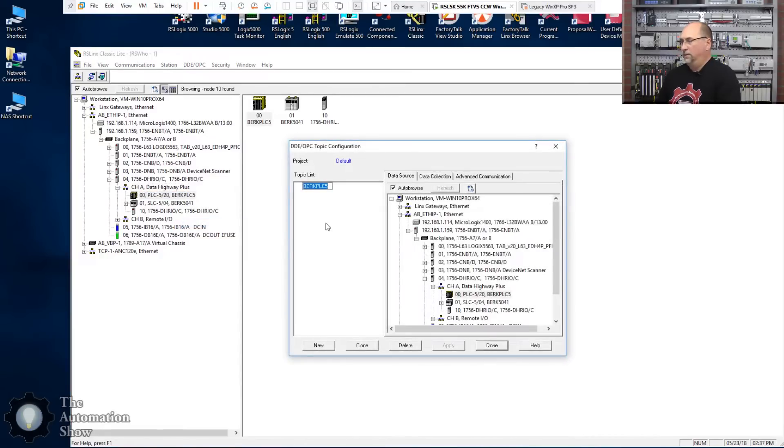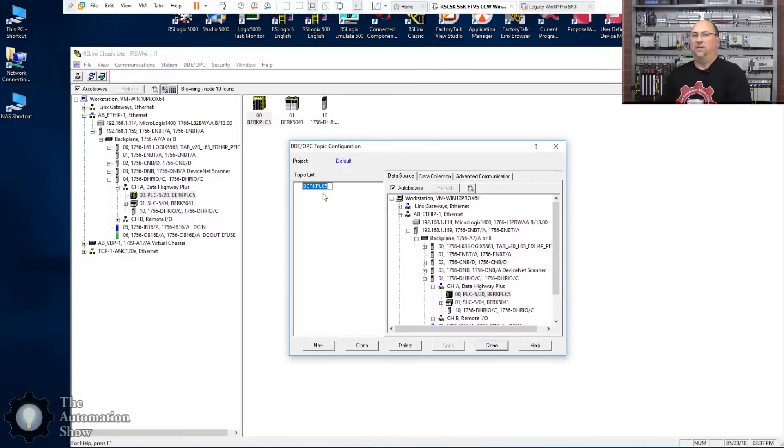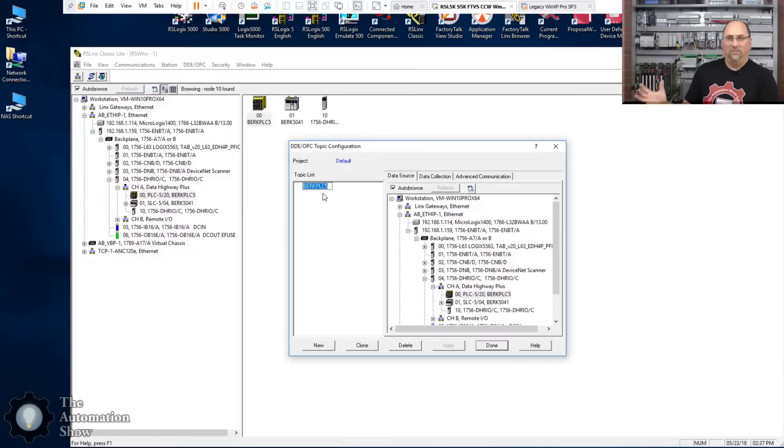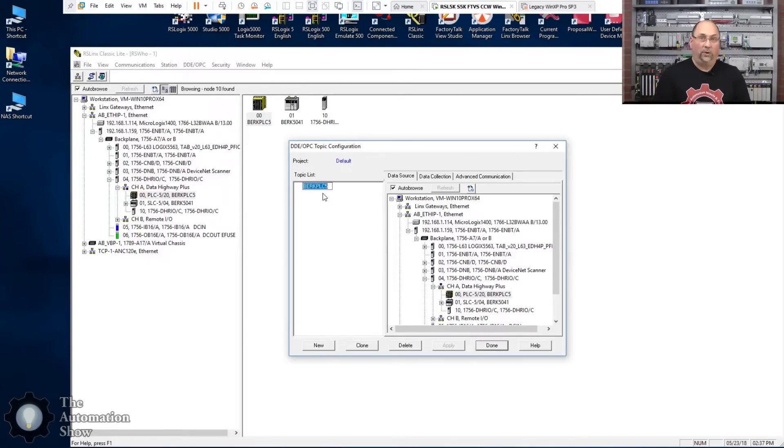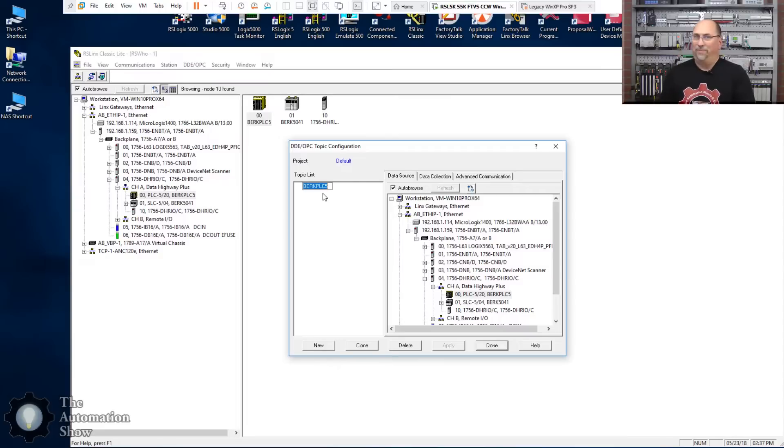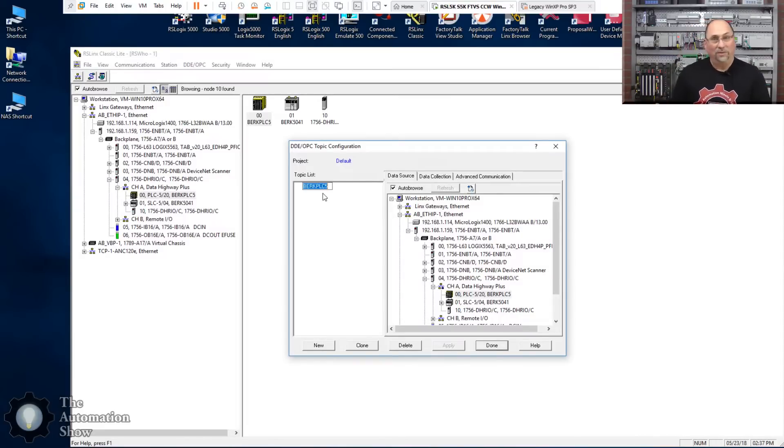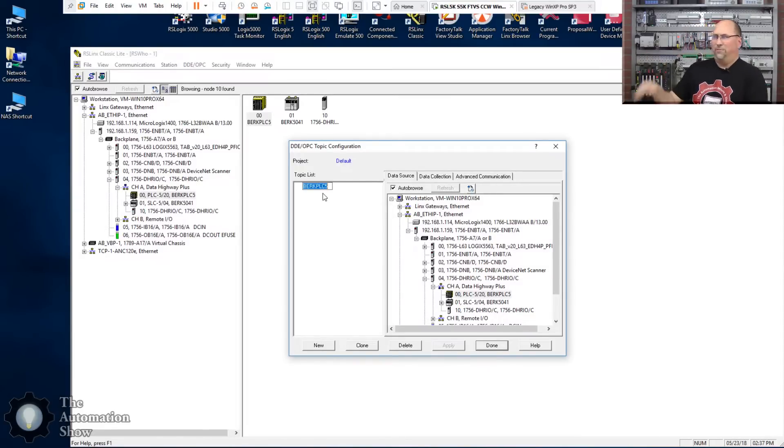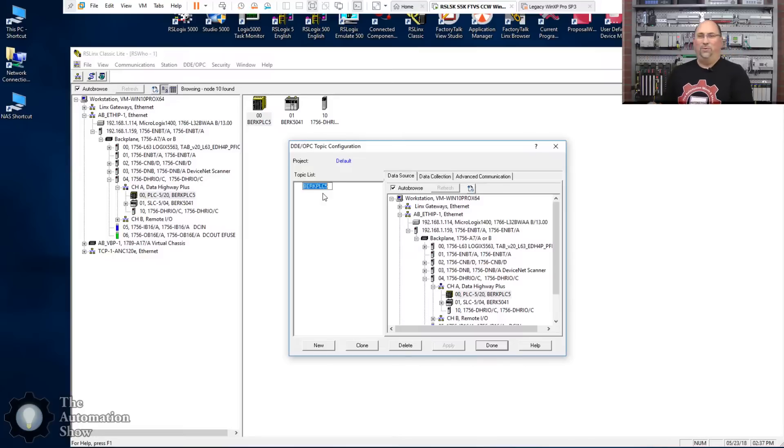So very similar to what we did with RSView 32 is what we're going to do is start by creating topics. These are called shortcuts in FactoryTalk Linx or RSLinx Enterprise, but in RSLinx Classic they're called topics. So I'm going to just right click here, create new DDE/OPC topic. Now look, you can see it's giving it a name based on the name of the controller, but notice how this list is empty.